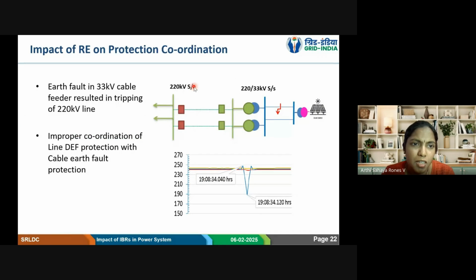And next is the protection coordination related issue. So this can happen in a conventional system also. Whenever there was a fault in one place, the upstream feeder should not trip. So here what happened, we have most of these 33/66 kV from the RE plants, they are out of cables. So there was a fault in this interconnecting cable. And for that, the 220 kV system directional earth fault protection maloperated, meaning there was no coordination between this overcurrent, and usually 33 kV it is overcurrent only. And for 220 kV, only the earth fault is overcurrent. Otherwise, it's distance or differential.